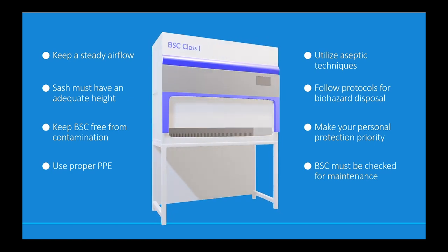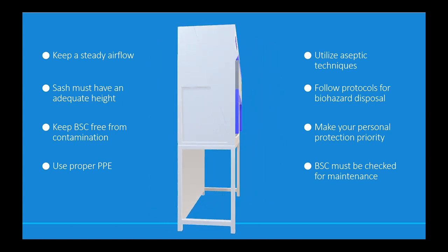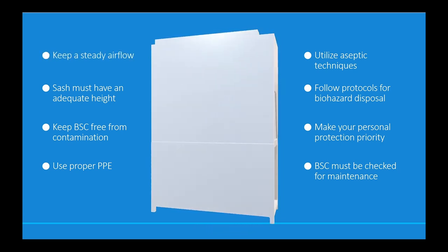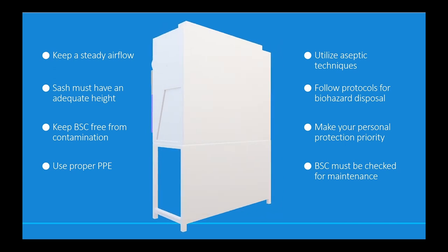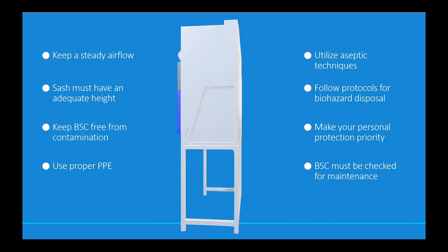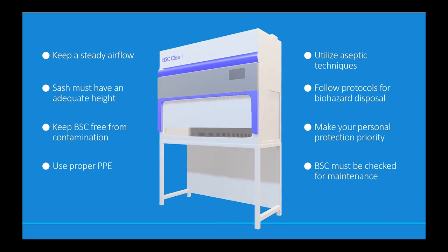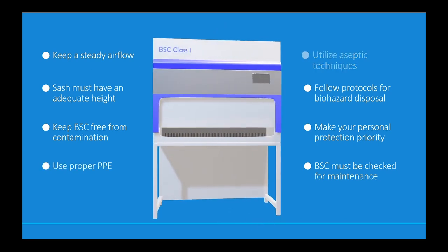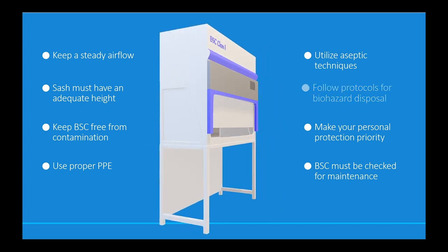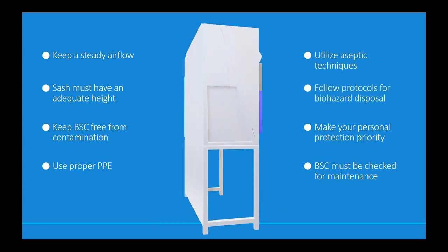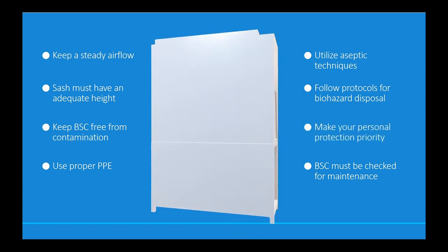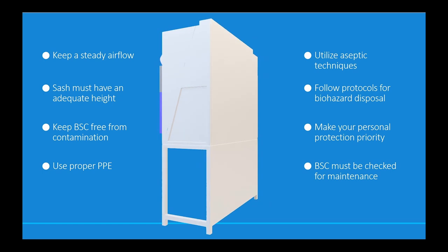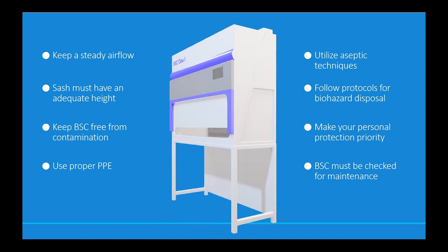Finally, some points to keep in mind while dealing with biosafety cabinets: maintain steady airflow, ensure the sash is at an adequate height, keep the cabinet free from contamination, use proper personal protective equipment, utilize aseptic techniques, follow protocols for biohazard disposal, make personal protection a priority, and have biosafety cabinets checked for maintenance on a routine basis by a biosafety officer.